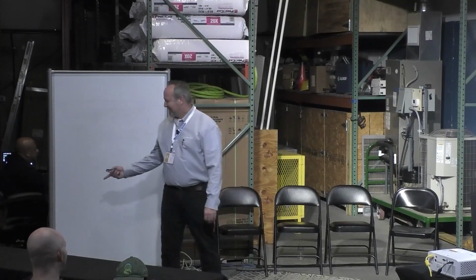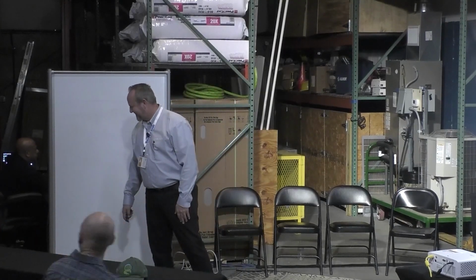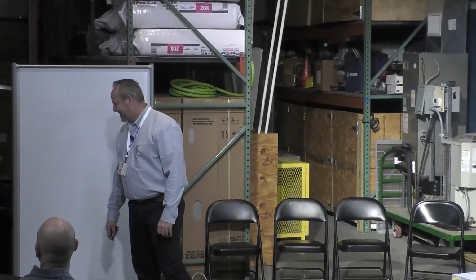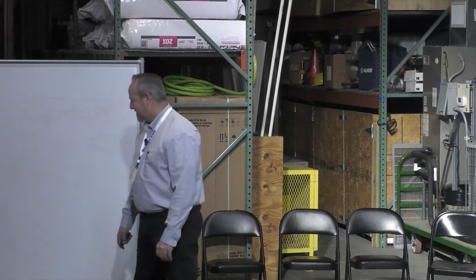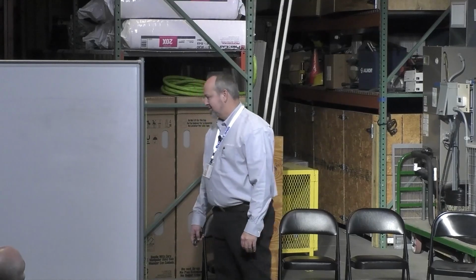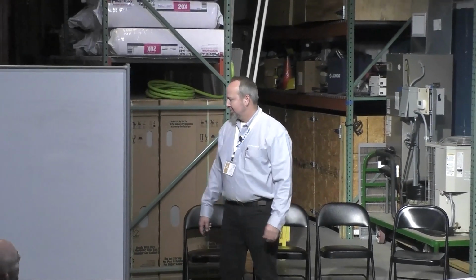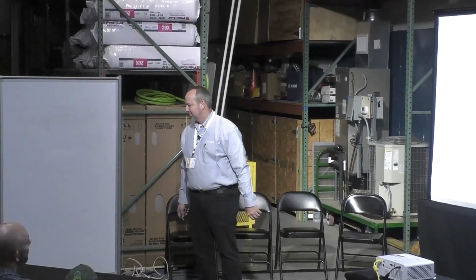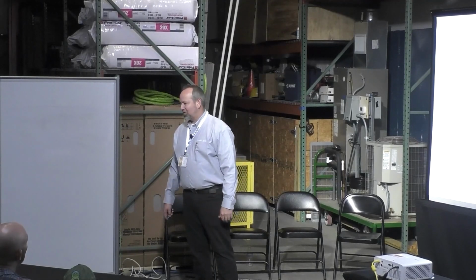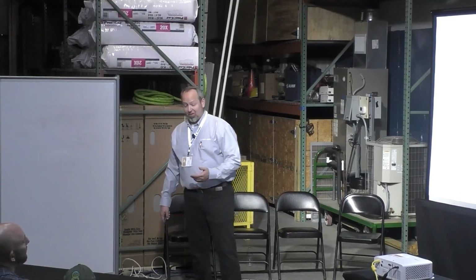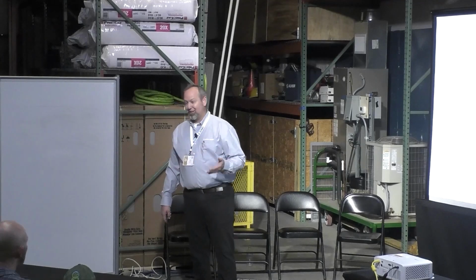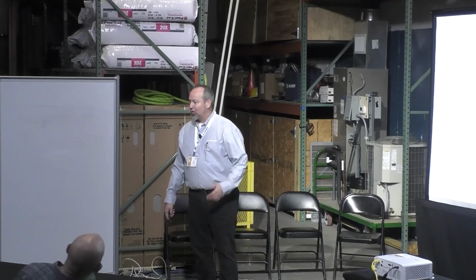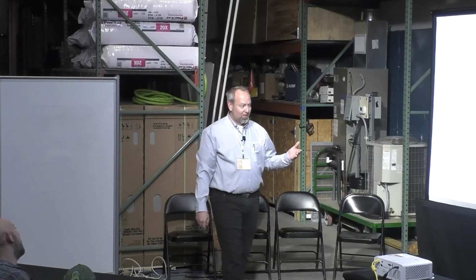Question online? My question online was, is this the main issue you see with the coil before the furnace? The coil makes so much more moisture, it corrodes the furnace boards that aren't as protected the way they are in an air handler. Do you have any way to mitigate that? So the comment is that there's additional moisture you're dealing with at the furnace board whenever the coil is before it.